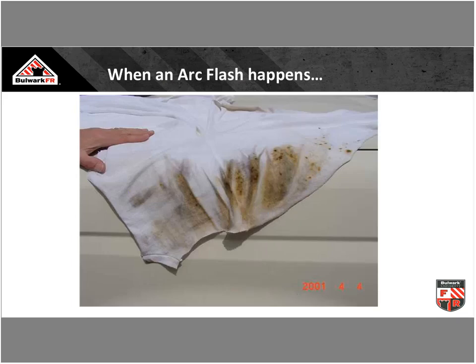Here's one of the telling things. When we look at this, this is his undergarment. Now, are we allowed to wear 100% cotton underneath our FR arc-rated clothing? Absolutely. Cotton, silk, wool, natural fibers can be worn underneath our outer layer, our shirt. You can wear cotton, silk, or wool underneath, or wear nothing underneath. We don't want to be wearing meltables, so this is fine. All the standards say there's nothing wrong here.